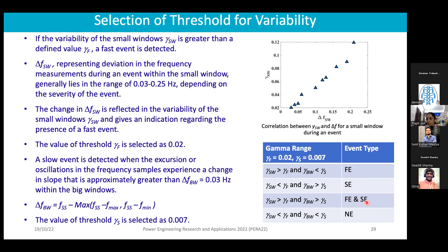If there is a change in slope greater than this within the big window, it indicates that some oscillations are going on or some slow event is happening. Similar analysis was done, and we identified that the threshold for the big window should be selected as 0.007. So if the gamma variability of a small window is greater than gamma f, and variability of the big window is less than gamma s, this is a fast event. If gamma SW is less than gamma f and gamma BW is greater than this threshold, it is a slow event. If both cross their thresholds, it is fast and slow event both. If both are within threshold, no event is happening.